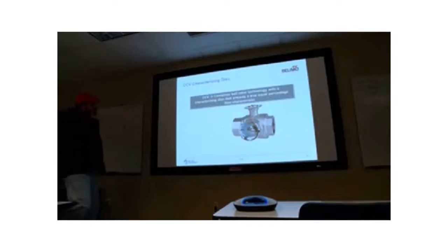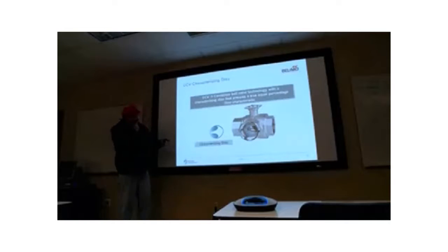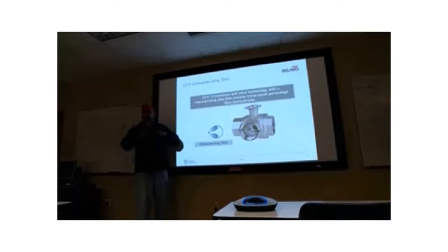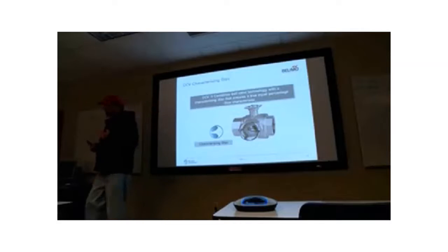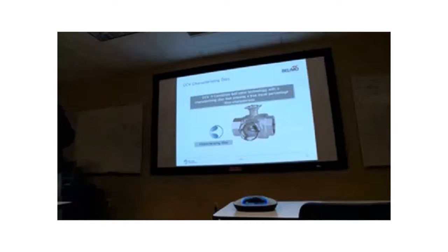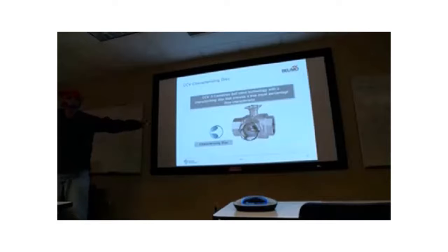We'll go back to a little bit of the design stuff here. This is a 3-way CCV. Remember I talked about the characterizing of the valve? Back in 1998, when we got into the valve business, the things being used to control flow were like a globe valve. Back in 1995, this is what you put on your VAV reheats. It would be either a 2-way or a 3-way globe valve. This is an expensive machine. It's twice the cost of these.